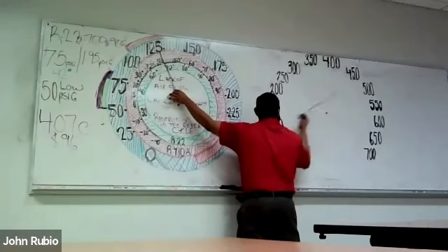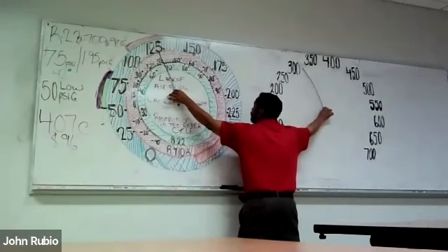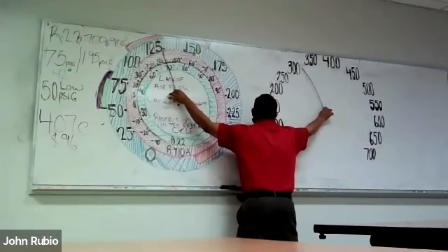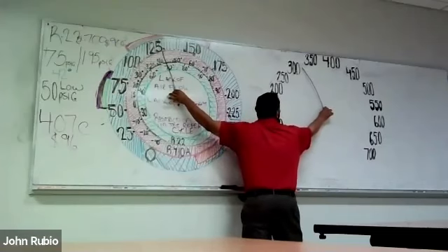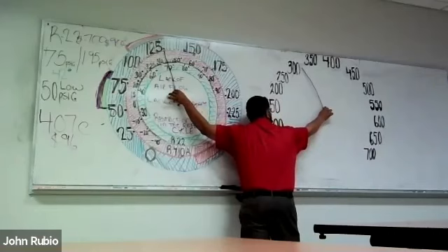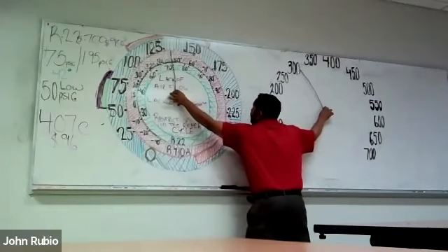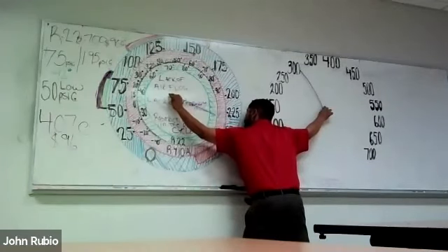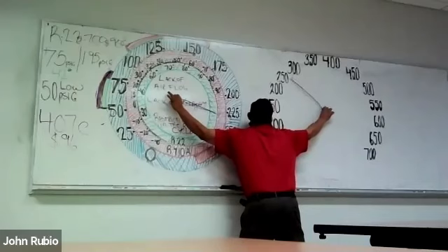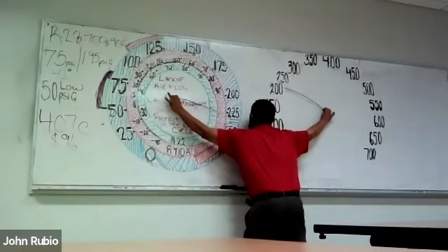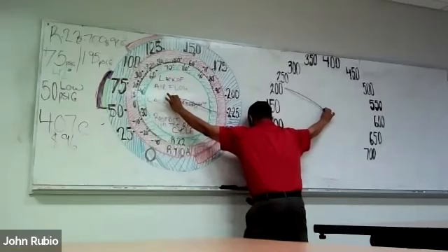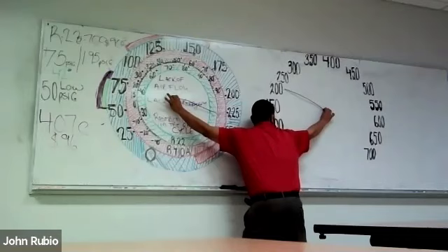So let's notice what happens when we are 125 over 300 and we're congruent needles. What happens when we equalize? Someone give me an equalized typical pressure for 410A. 221 to 234. Thank you, sir. 221, 234. Are my needles congruent at all? No. But are they equalized? Yes. Is my compressor off? Yes. Is this how equalized needles should look? Yes.